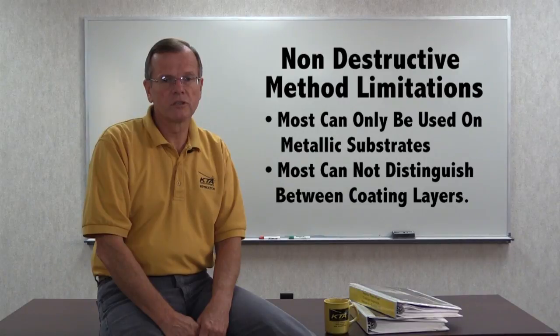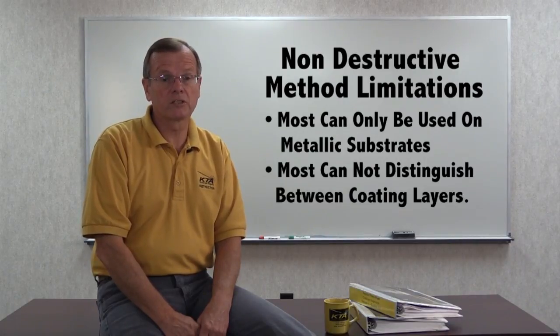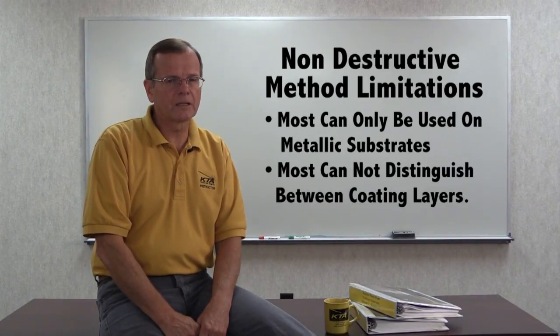Coating thickness is commonly measured using non-destructive gauges. However, those coating thickness gauges have a few significant limitations. They can only be used on metallic substrates, and most can't distinguish the thickness of individual layers after all the coats have been applied. They only measure the gap between the gauge probe and the metal substrate.